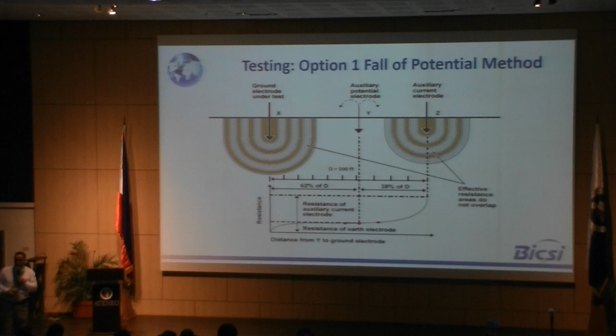So this is the testing for the fall-of-potential method. They just take it outright and say, once you test it, it drops at 62% away from the rod. But if you plot this, this is the graph you would get. But then look at where it levels up, that's your rating. If you cannot achieve this in the test, like an S-curve, then the system you're using is wrong.